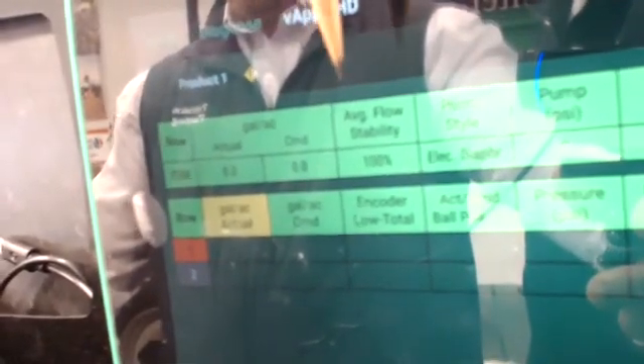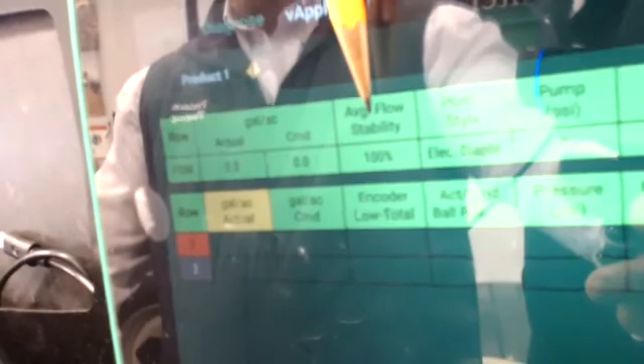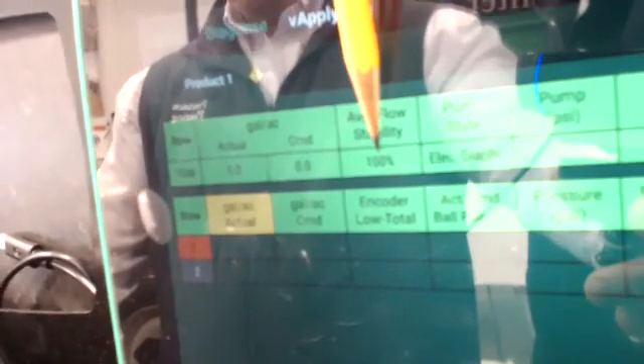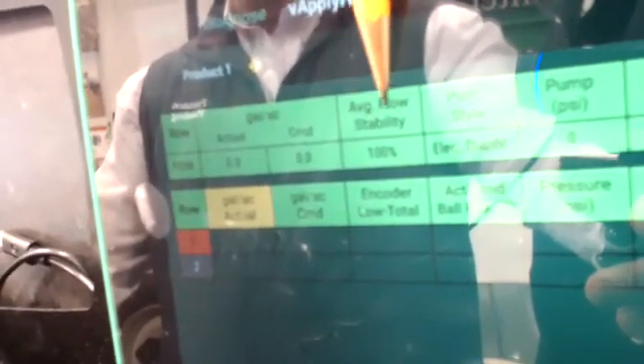So I just want to point out a couple things here quick before we close this session out. So this average flow stability here, this is for the master module, since it's above the dark line. If this number gets below 85% flow stability for the system, the HDs will start to try to compensate for some of the choppiness that's causing that lower flow number. So below about 85%, they'll start trying to compensate, and you will possibly see that on your field view where if you pull up the liquid map, you'll start to see some choppiness as that flow stability degrades in your application map.